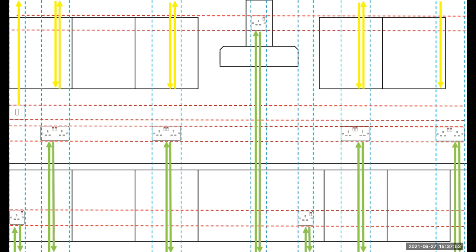So here's what I would have done. As you can see, it's a lot easier to see what's going on. You only have to drop an accessory off the wall to see which way the cable goes, and you would know that it travels straight to the floor, ceiling, or accessory in accordance with regulation 522.6.202. It just makes it so much easier for everybody involved to avoid cables. All this bit in between now is free for somebody to secure fixing it.